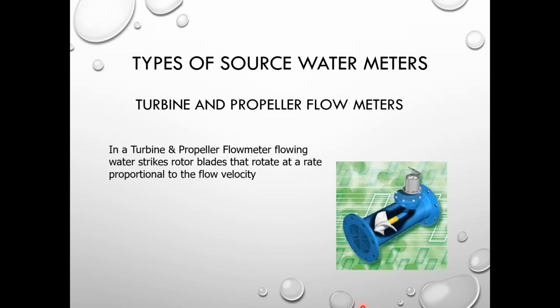These meters do need to be maintained over a period of time. The gears and the propeller, well, the bearings in them will start to get gunked up and they need to be rebuilt. Most of the time we'll find out when the flow meter just starts reading inaccurately and we get a call from somebody saying, hey, this meter's not running right. So we'll have to go out and have that rebuilt. A lot of times you can just drop an assembly in.